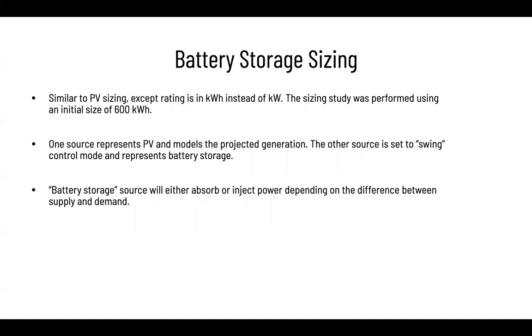So next we decided to perform some battery storage testing. We wanted to make sure that the initial sizing that we decided on would be enough to sustain the demand during periods where the PV is not producing any energy. So we went with our initial sizing of about 600 kilowatt hours. In order to model this, we didn't use a detailed battery model. Instead, we used two ideal power sources or generators in ETAP.